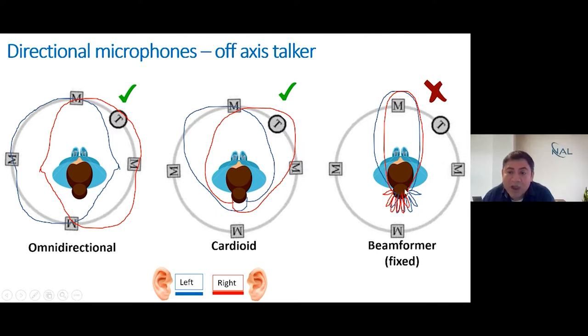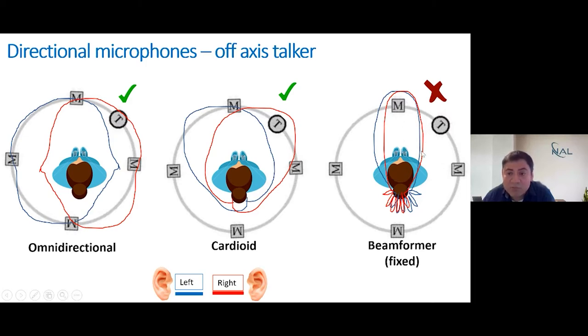The problem comes with higher-directionality systems. Because of the way they are designed, when the target sound moves to the right and off the main axis, it is no longer in the pathway of this narrow directionality. As a consequence, the person is not able to hear that sound effectively, and in fact the system starts to emphasize something else like noise. In this condition, this type of technology will not be positive for the listener and will produce a negative effect.